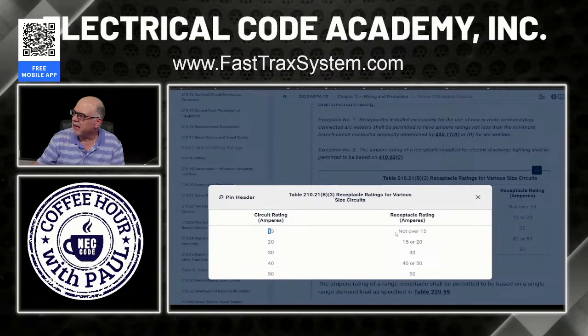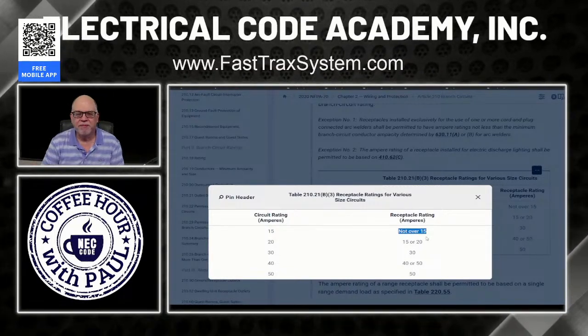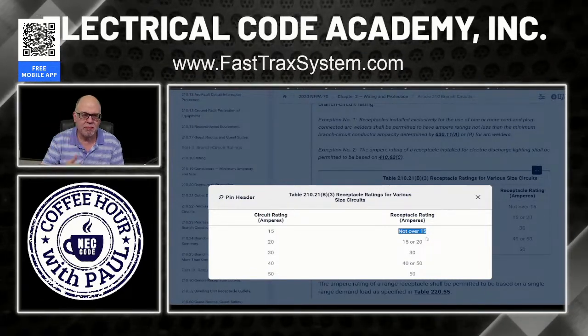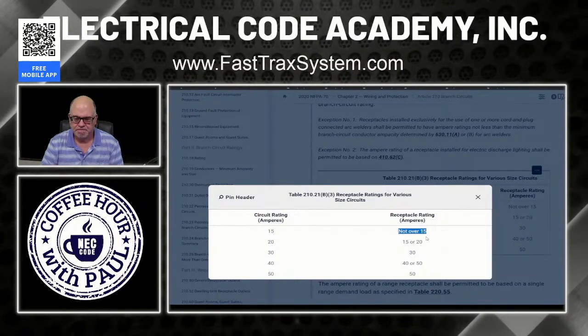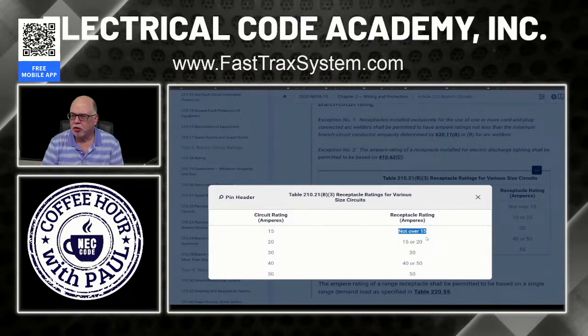Then the receptacle rating right here, not over 15 amps. So on a 15 amp branch circuit, the maximum duplex receptacle that we could have on this is 15 amperes. Make sense? So you're doing that bedroom.